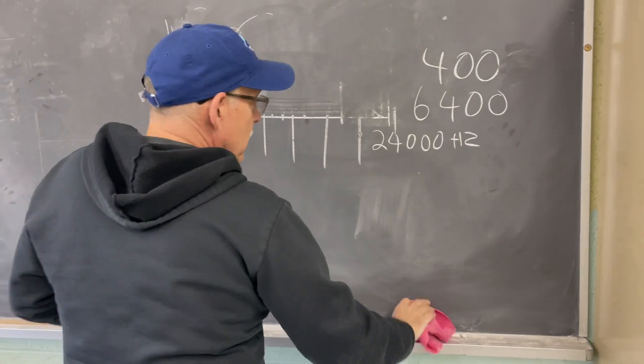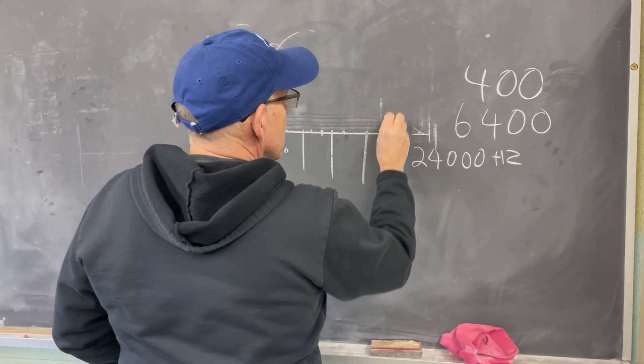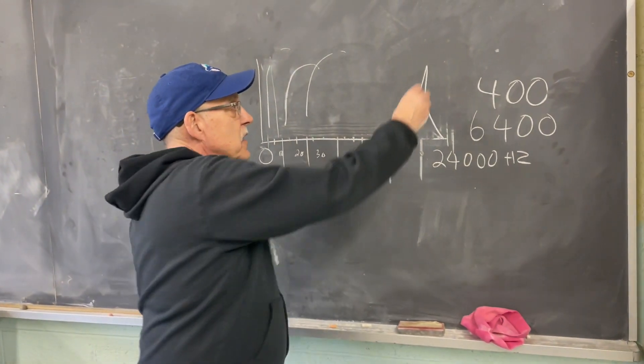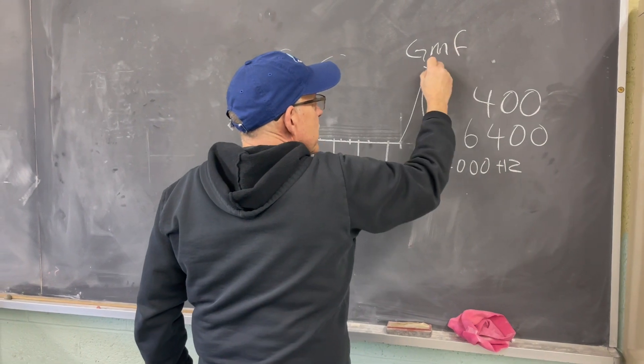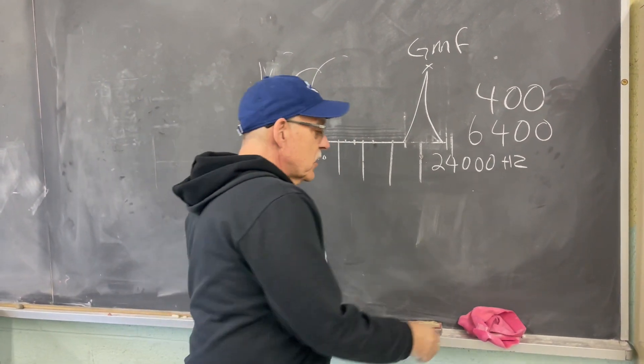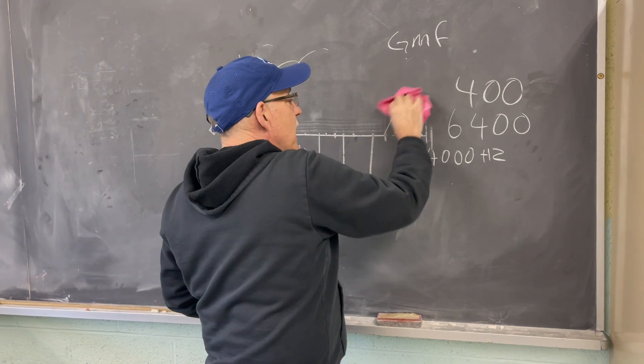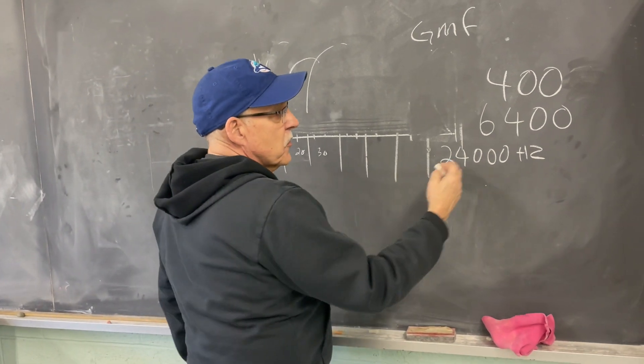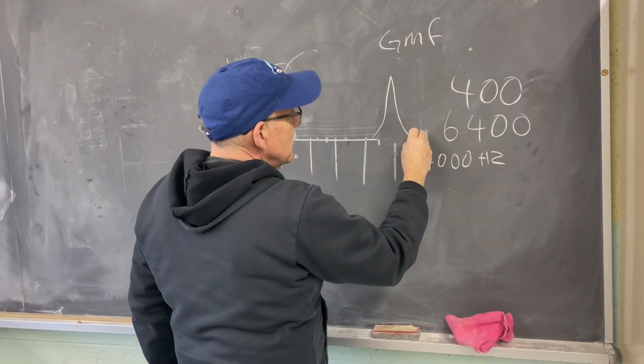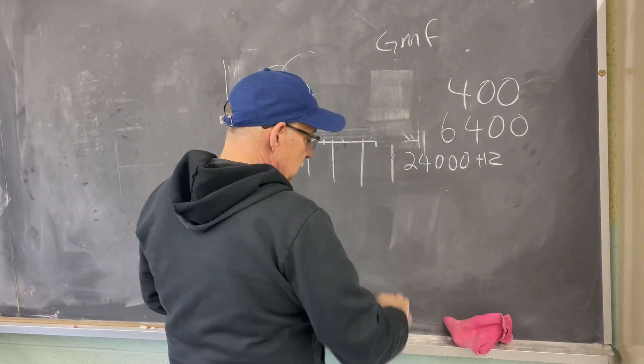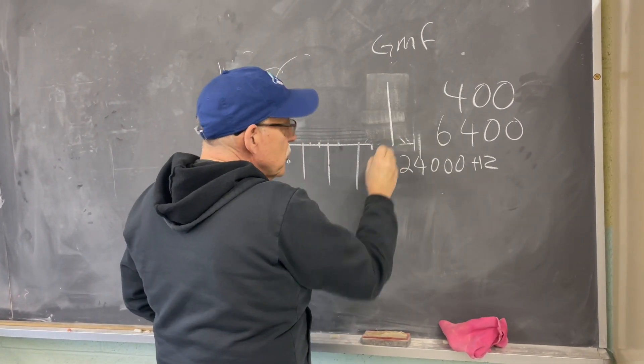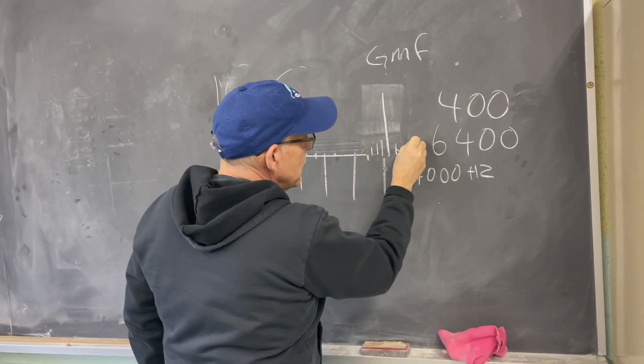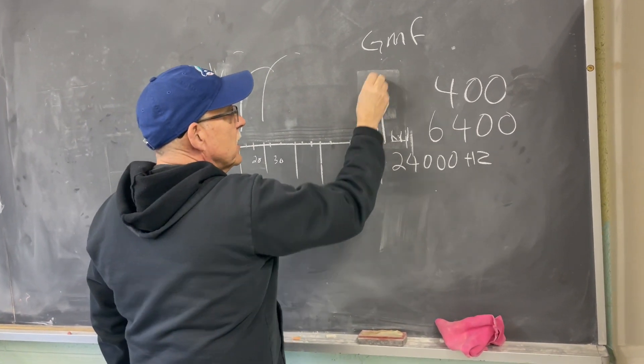At 400 lines we can identify the gear mesh frequency, but with gear mesh analysis we also look at the sidebands around that primary frequency — sidebands are a way to tell the severity of the problem. At 6400 lines, the spectrum now shows the primary gear mesh frequency clearly with the small sideband lines around it that you simply wouldn't see at 400 lines. The old picture at 400 lines would have looked like one wide peak, and all that sideband information in between was missed.